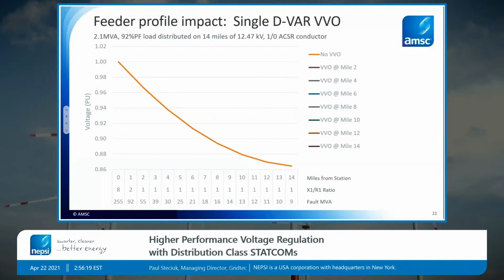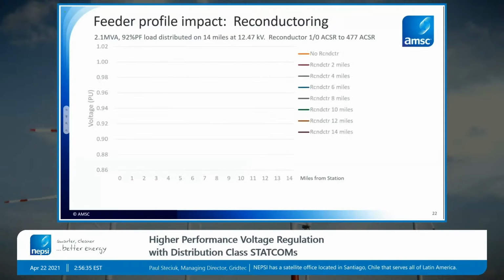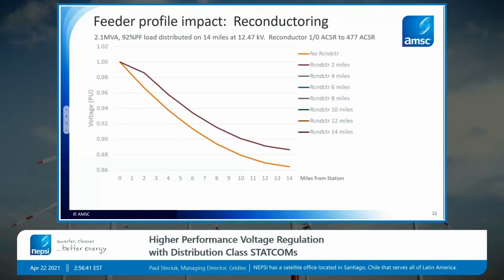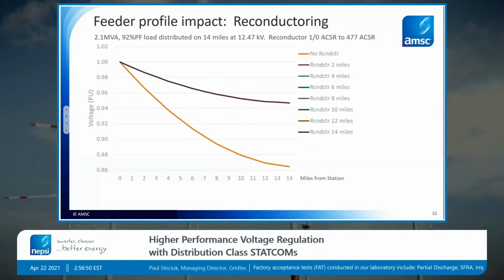The same concept we can now look at in the context of now reconductoring a feeder. So we're going to go through that same idea now with basically 2 miles of reconductoring from a 1-aught conductor to an ACSR 477. And here's that same profile, baseline. Now we're going to reconductor the first 2 miles and keep reconductoring another 2 miles as we go out. And the striking thing about reconductoring from a voltage standpoint is that it has a very similar impact as the VVO. So reconductoring also provides thermal capacity, of course, but when it comes to just being able to improve voltage, the impacts are quite similar.